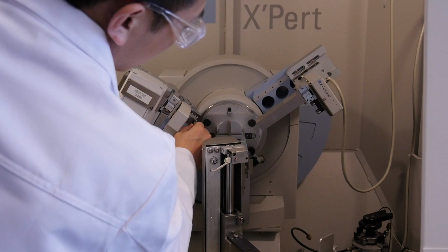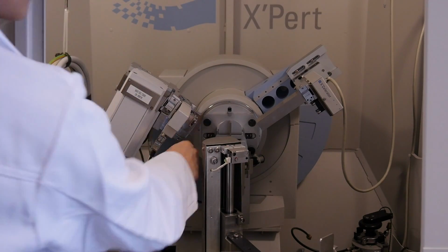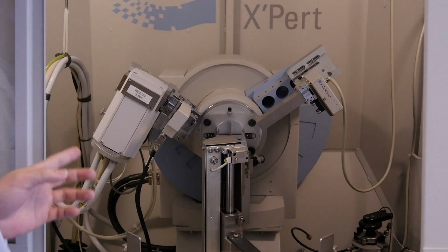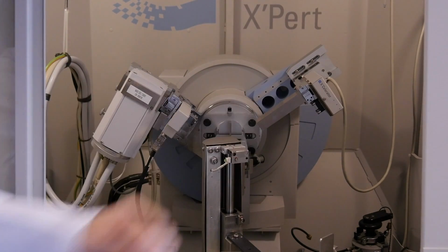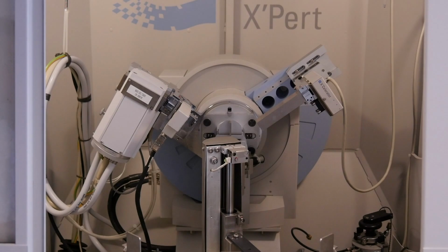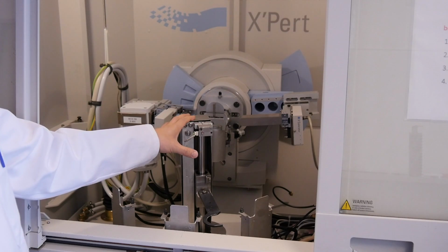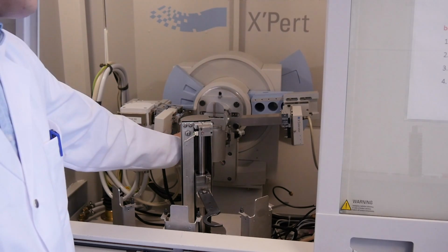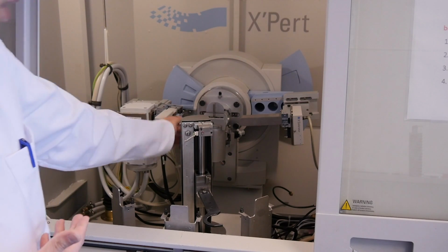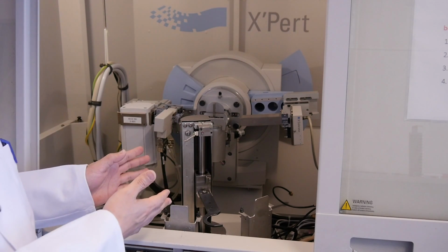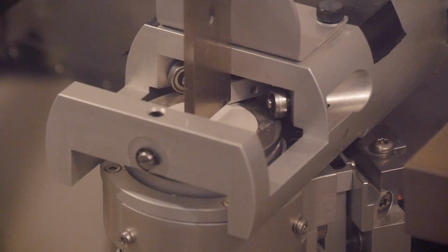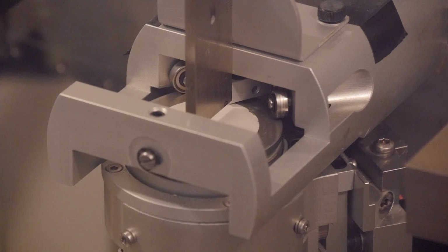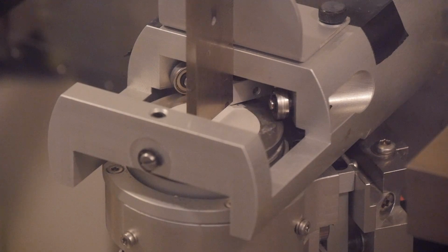Sometimes, a beam knife just on top of the sample will be applied to remove the scattering of the X-rays at lower angles, which is important for samples presenting peaks at lower angles. Some of the sample stages are equipped with a sample spinner, which rotates the sample during the data acquisition. Whenever the spinner is available, it is recommended to spin the sample to improve the statistics of the particles.